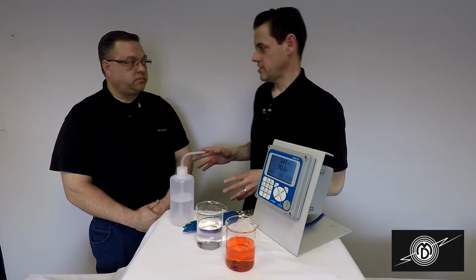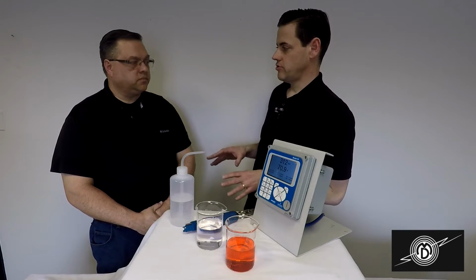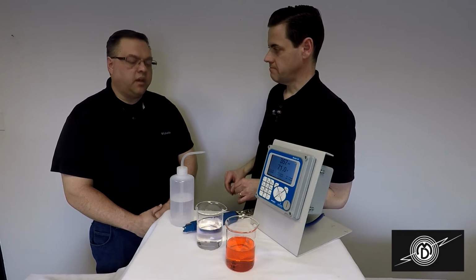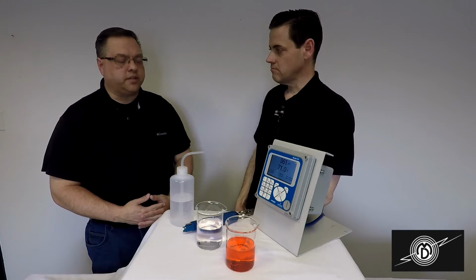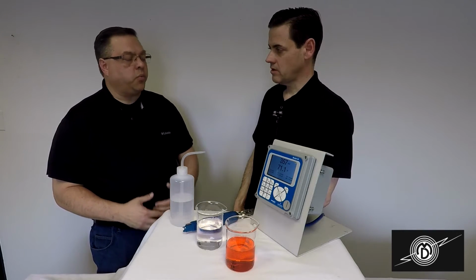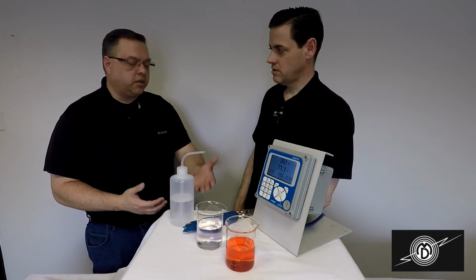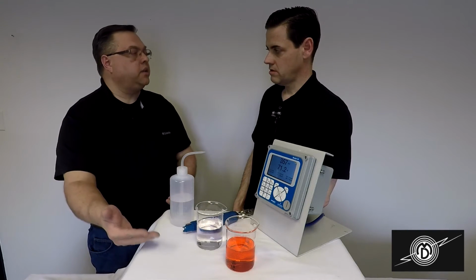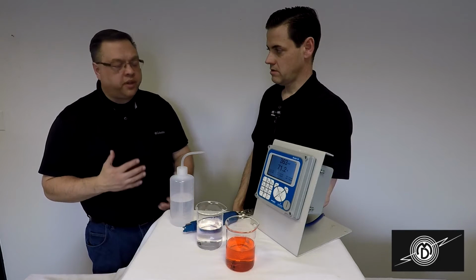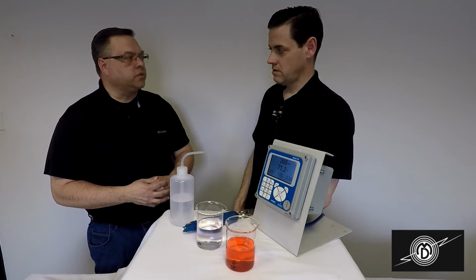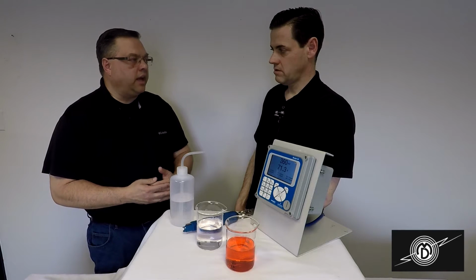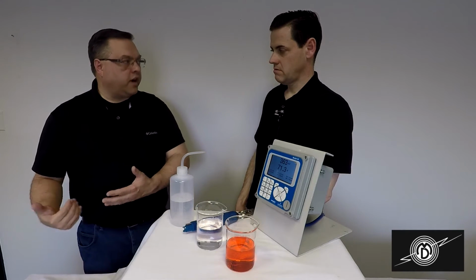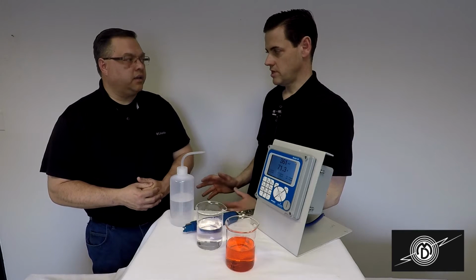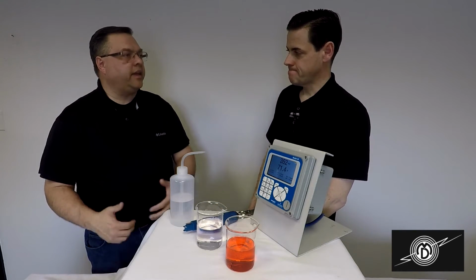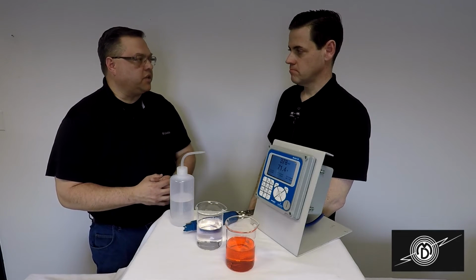So a couple more questions, Mark. How often should the system be standardized? That's going to depend on each and every process. What I recommend is you start with once a week, pull the probe out, clean and rinse it, and place it in your standard solution. If you're within plus or minus 20-25 millivolts of your process standard, then you should be good and move on to the following week. So no need to re-standardize at that point? Correct. If you're more than that, then you'll want to redo a single point standardization.